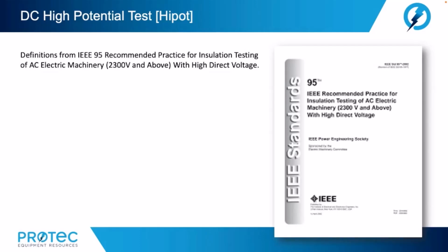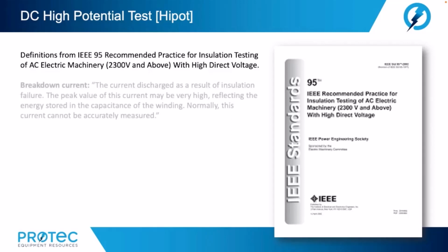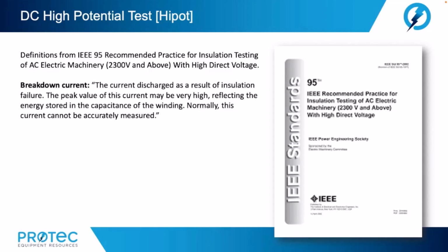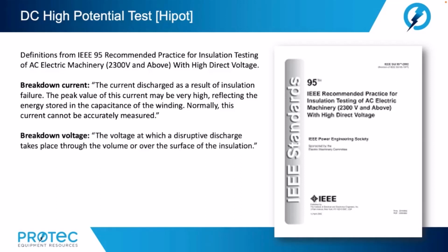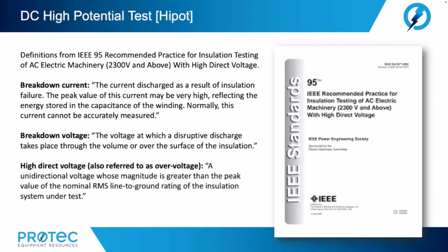Now let's look at definitions. Definitions from IEEE 95, recommended practice for insulation testing of AC electric machinery, 2300 volts and above, with a high direct voltage. The first definition we see is breakdown current: the current discharged as a result of insulation failure. The peak value of this current may be very high, reflecting the energy stored in the capacitance of the windings. Normally, this current cannot be accurately measured. We also have breakdown voltage. This is the voltage at which a disruptive discharge takes place through the volume or over the surface of the insulation. And we have high direct voltage, also referred to as overvoltage: a unidirectional voltage whose magnitude is greater than the peak value of the nominal RMS line-to-ground rating of the insulation system under test.